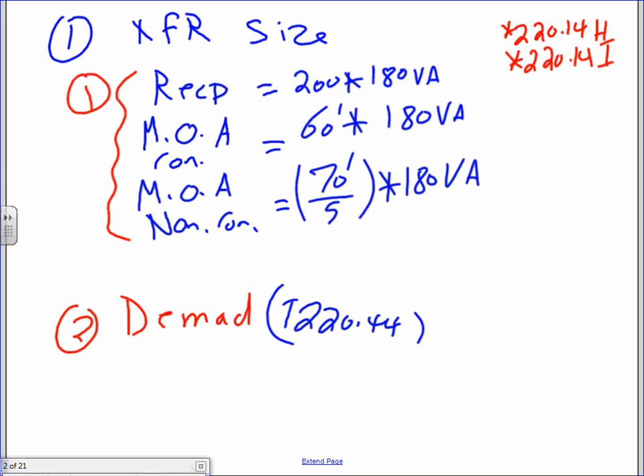Any comments, any questions about the multiplication that we did? Does it make sense? Yes? No? Okay. Then, my friends, after you do all this, you're going to add them all up, and you're going to end up with 49.3 kVA. I want to remind you, Adam, that I divided everything by 1,000, because when we size things, a volt-amp is meaningless, guys. When you size power transformers, you need kVA. So we multiply and add them up.